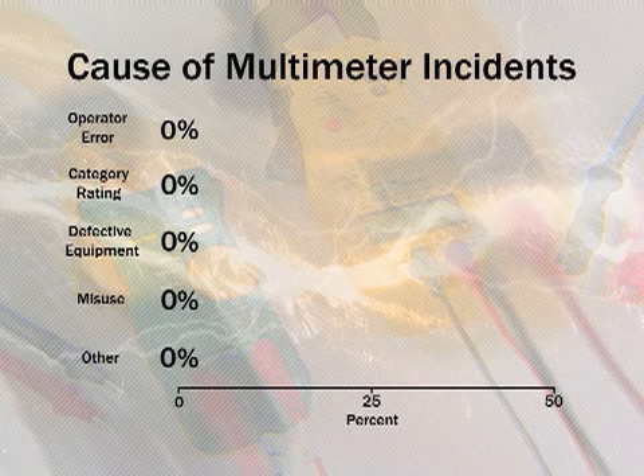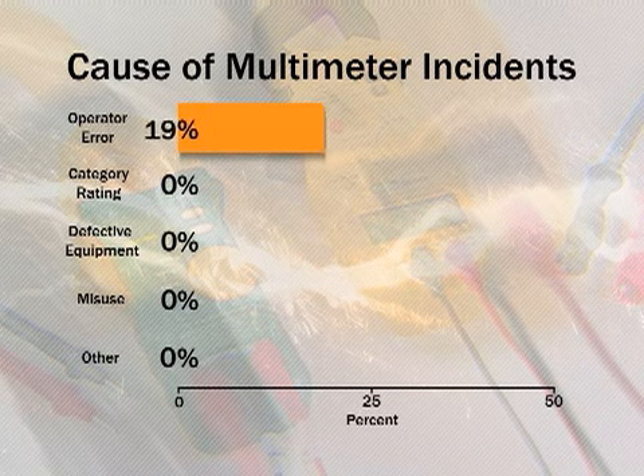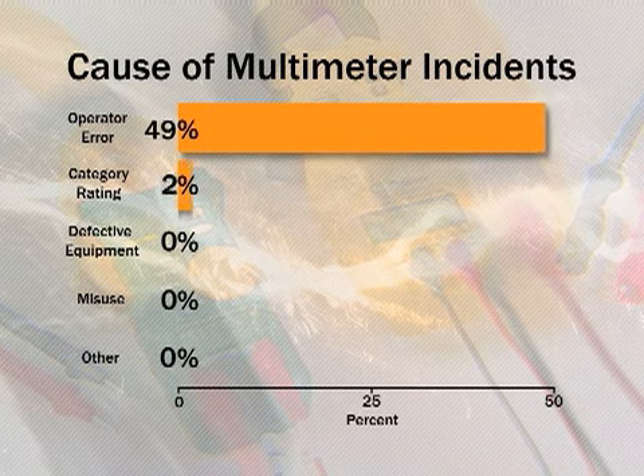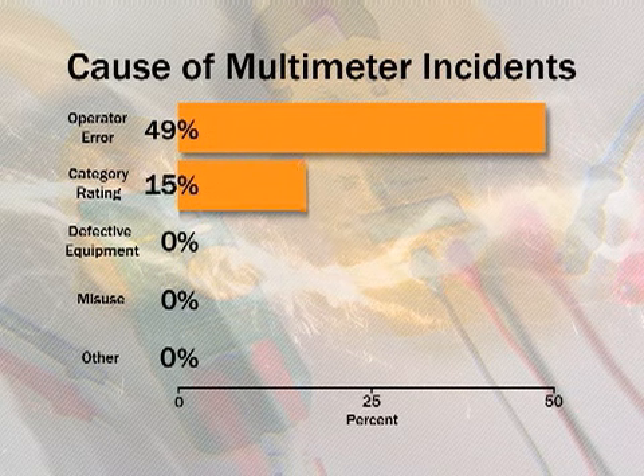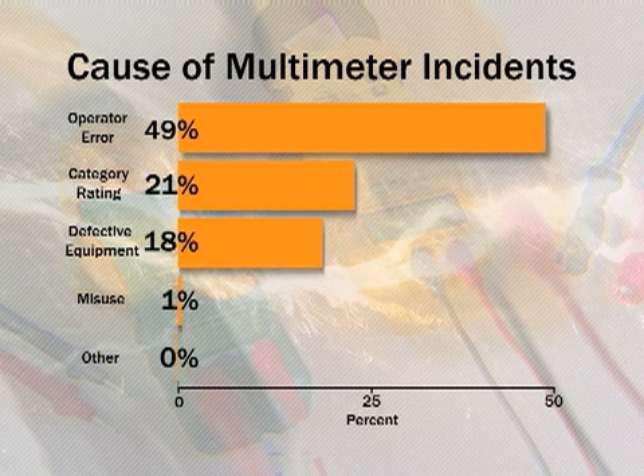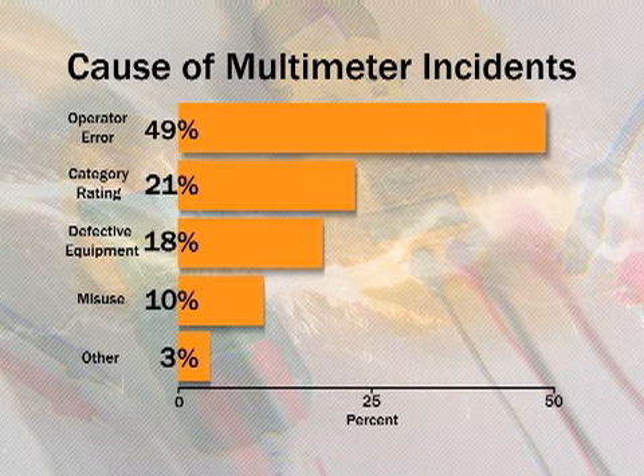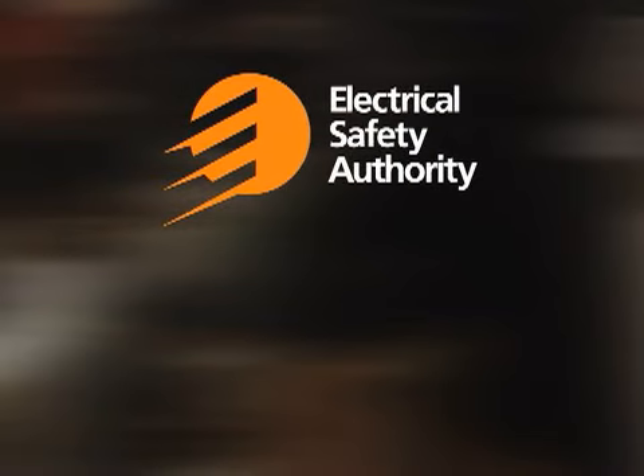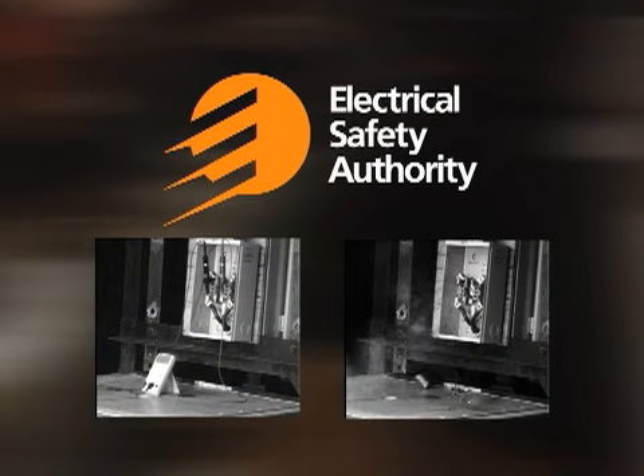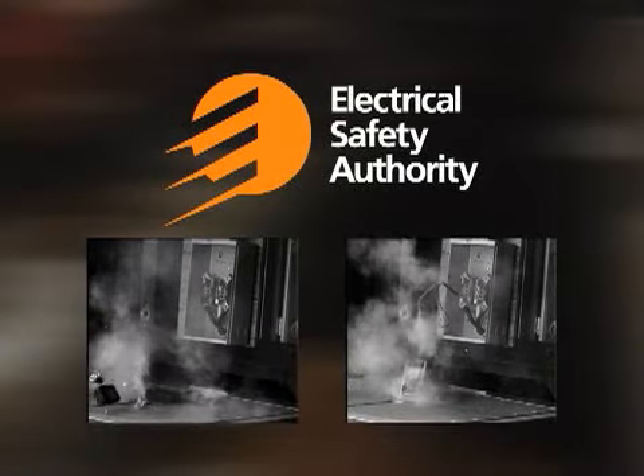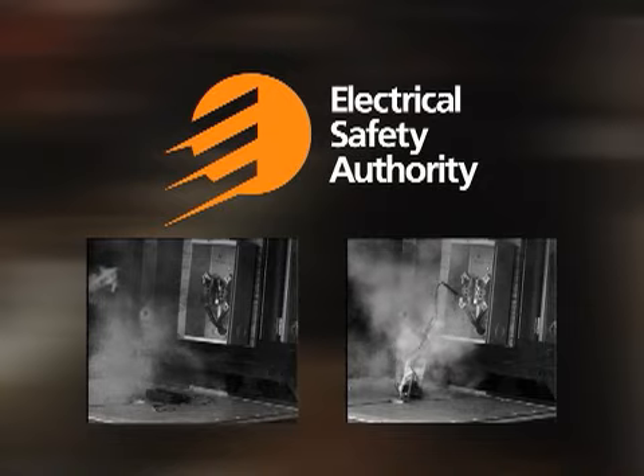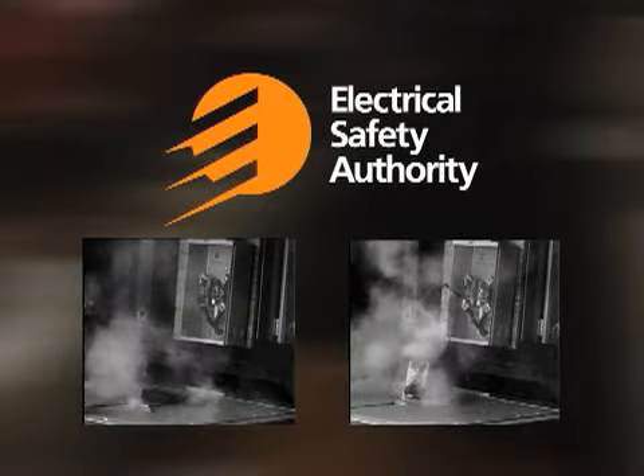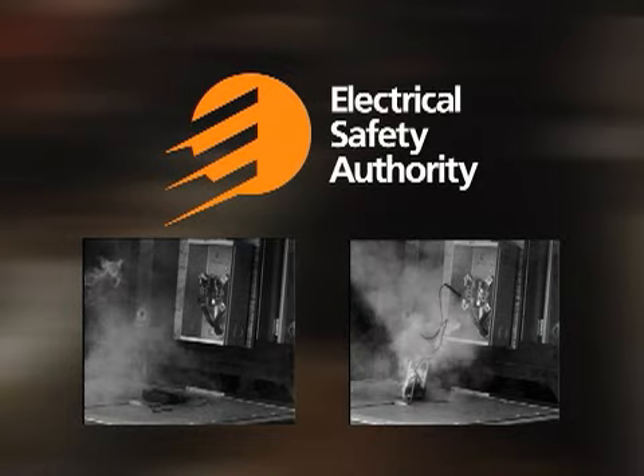ESA's survey respondents reported that injuries with multimeters occurred due to operator error at 49%, category rating at 21%, defective equipment at 18%, misuse at 1%. Recent studies and simulations commissioned by the Electrical Safety Authority conclude that the use of fused leads is a highly effective way to prevent possible catastrophic results if a multimeter is being used in an inappropriate way or experiences an internal failure.